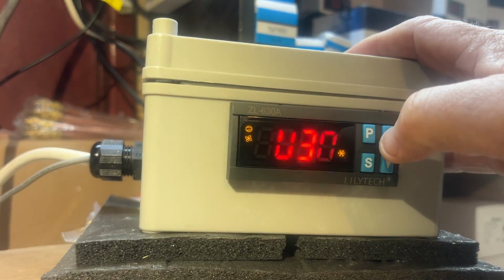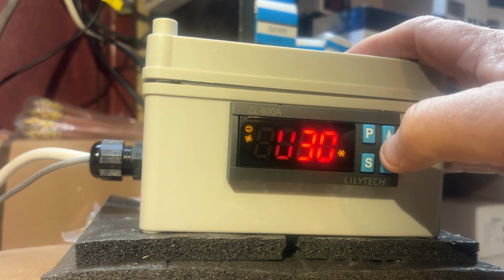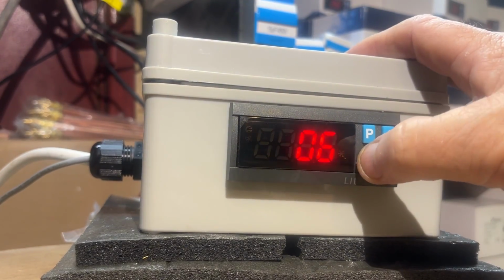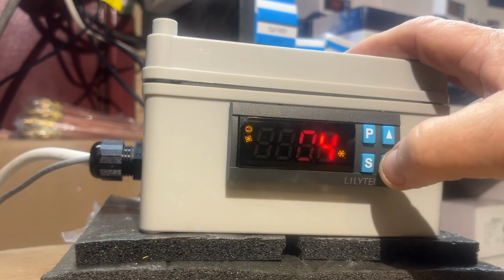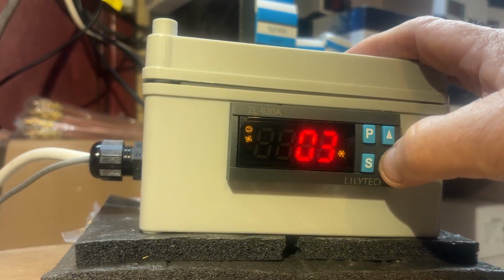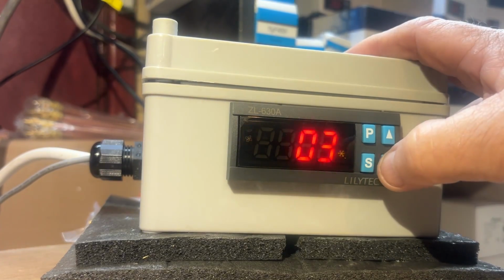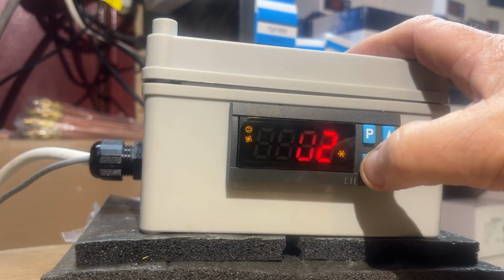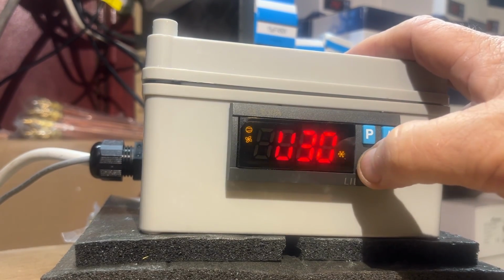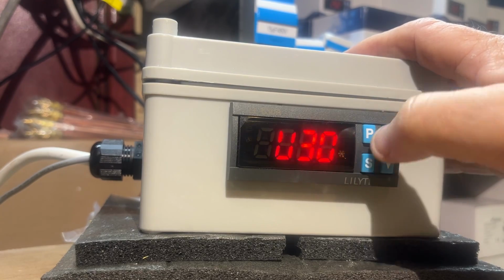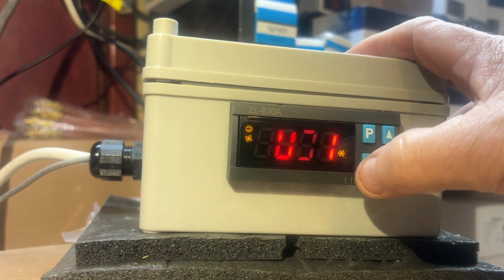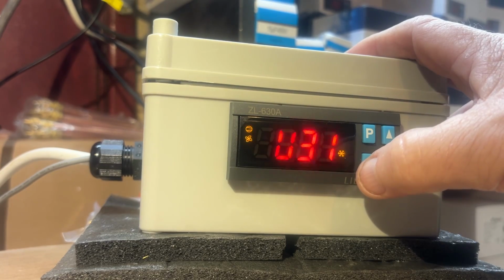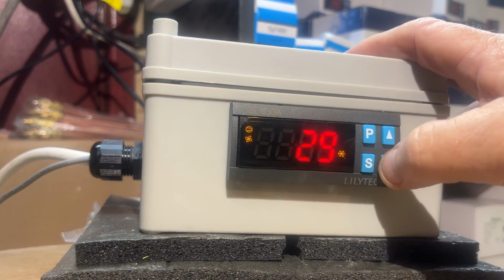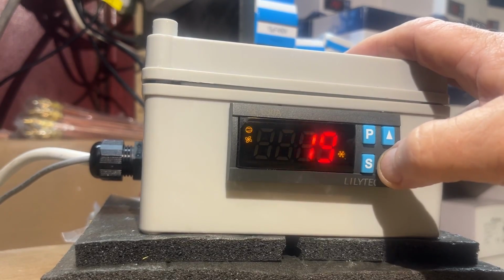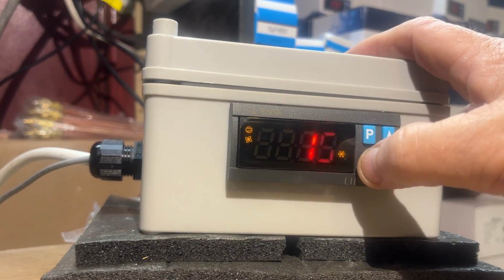Okay, and 30. 30 is the defrost period. Well, I would set this as a fridge. I would set this for every 2 hours, and I'll tell you why in a minute. Every 2 hours. And let's go to 31. And 31 is the time. I'll set that to 15 minutes. So it's going to defrost every 2 hours for 15 minutes.